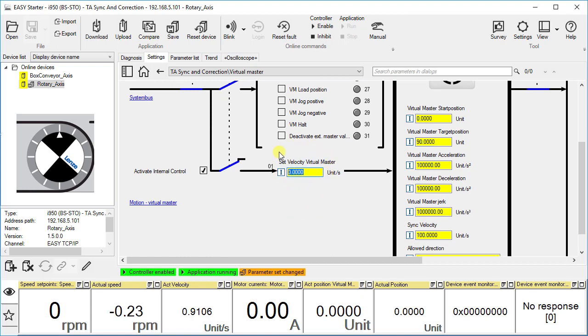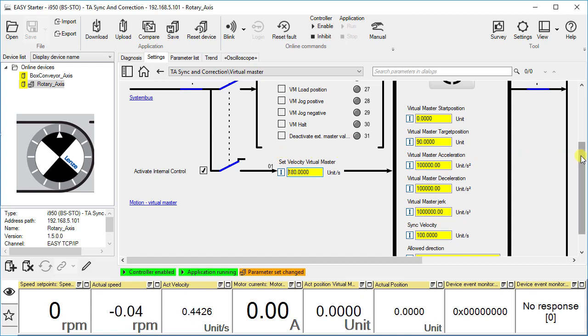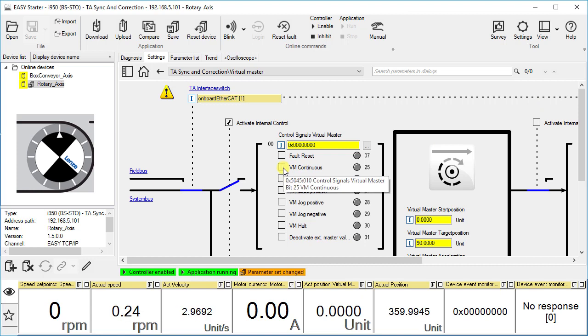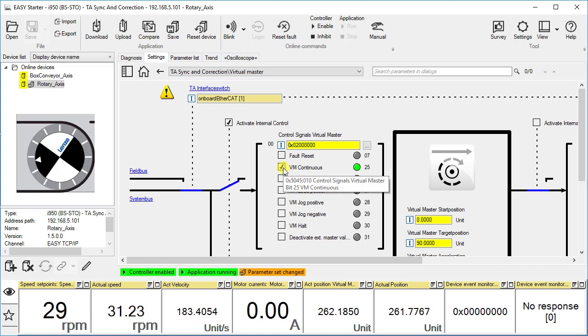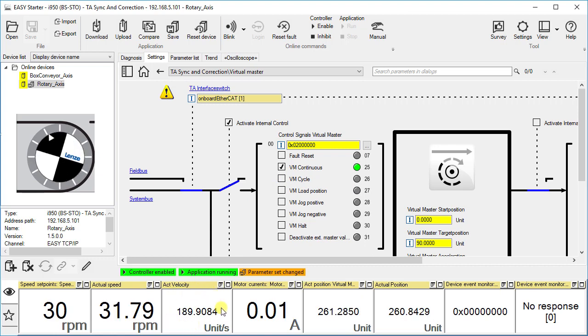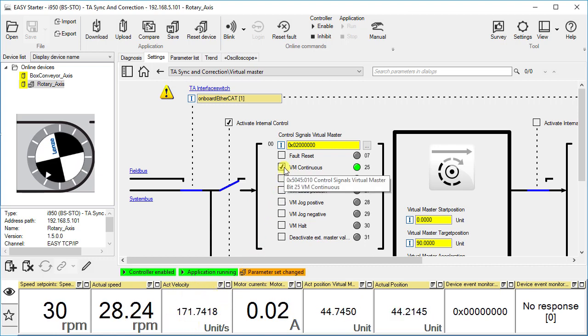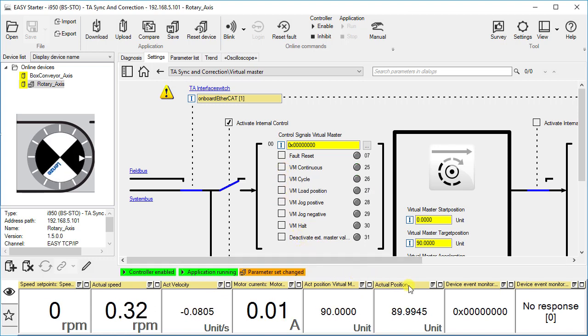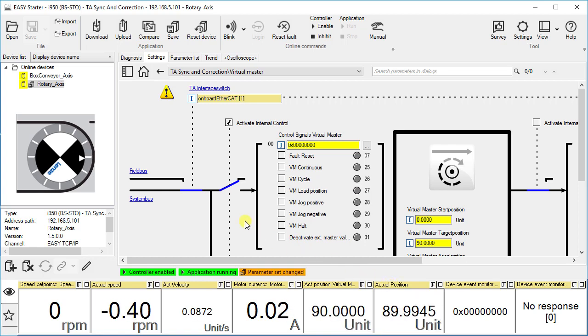You can set the velocity of the continuous mode here. We will make it 180 units per second. Now we will observe the target position behavior. Click onto VM continuous. The drive starts moving in positive direction with the velocity 180 units per second. As we uncheck the option VM continuous — that is, we withdraw the operation command — the drive does not stop immediately but stops after reaching the target position. This is how the virtual master works.